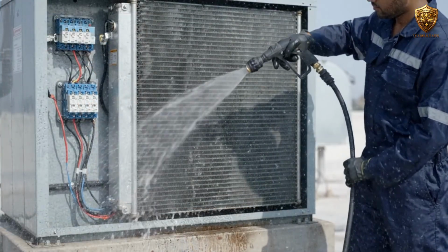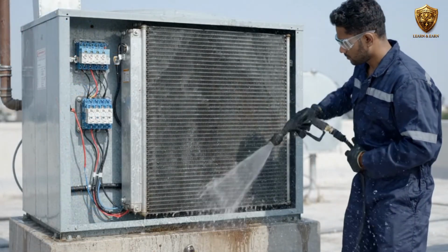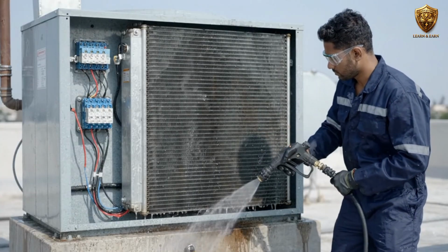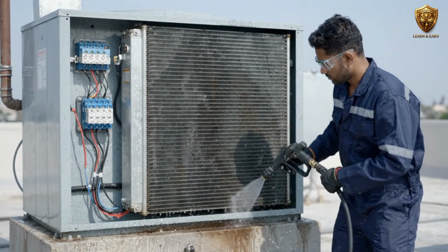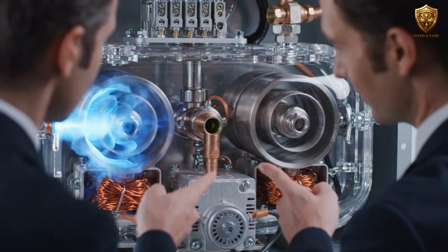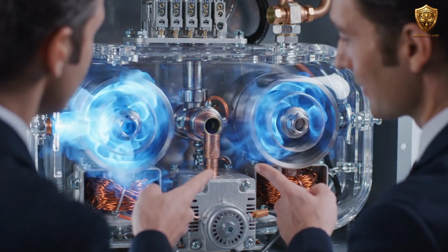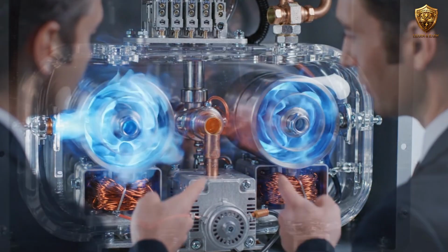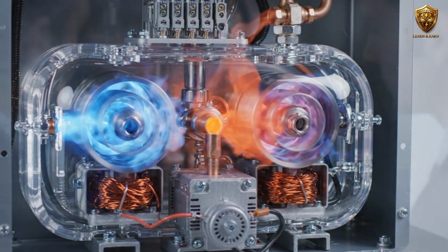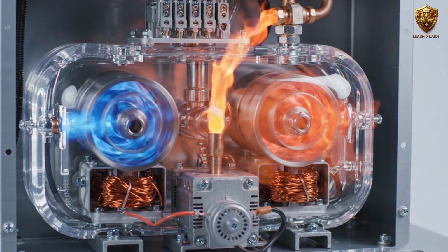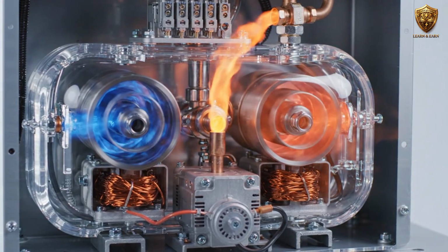High ambient temperature does not automatically mean the AC is faulty, but it can expose weaknesses that are not obvious under mild conditions. A good technician considers both the equipment and the environment in which it is operating. The compressor should usually be one of the last major components to blame, because many other problems can make a healthy compressor appear faulty. A compressor that does not start may have a power problem, a control problem, a capacitor problem, a contactor problem, or a mechanical or electrical compressor fault.